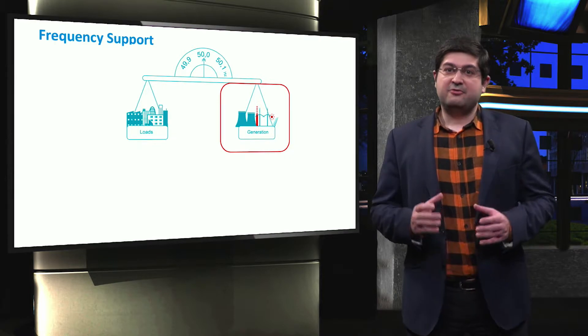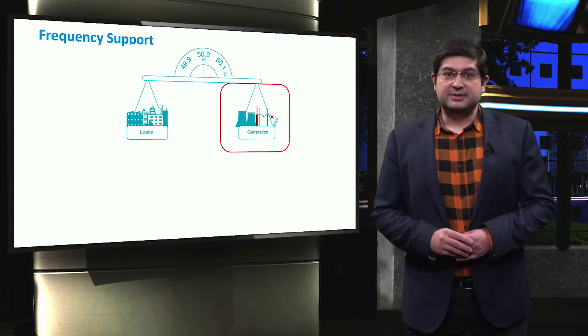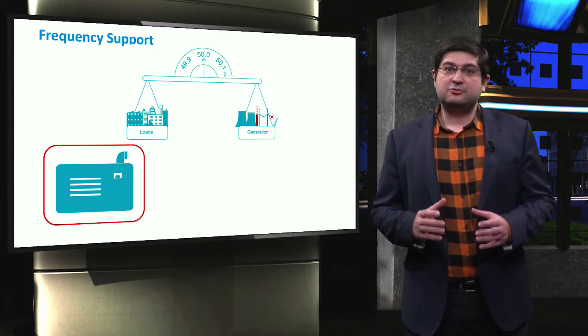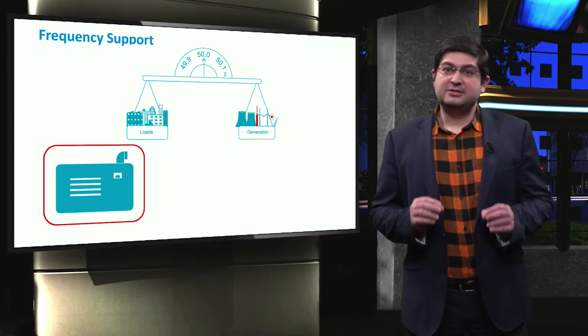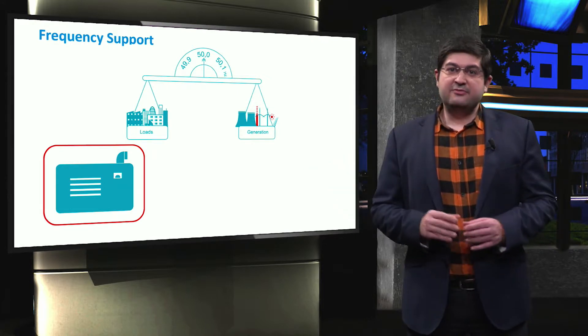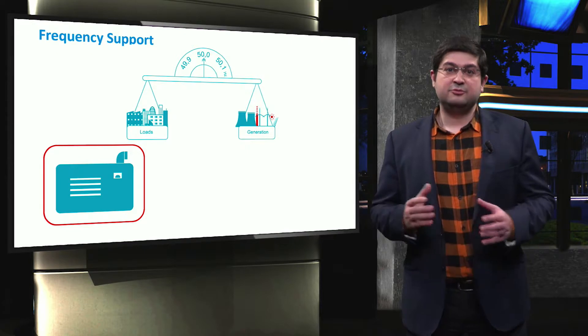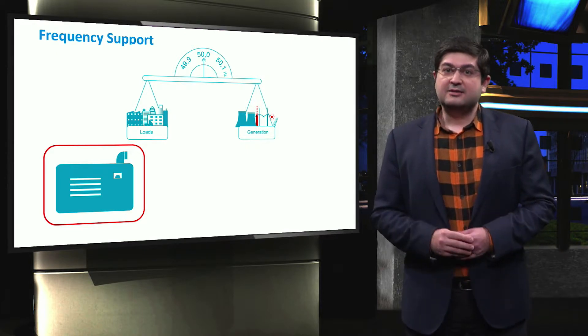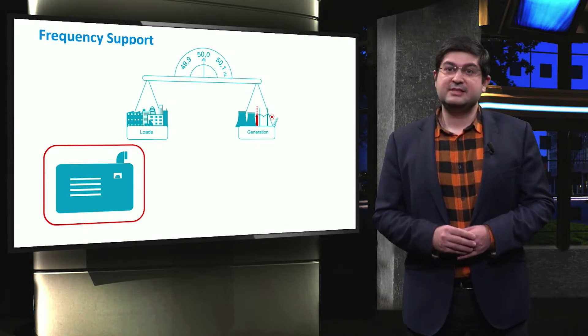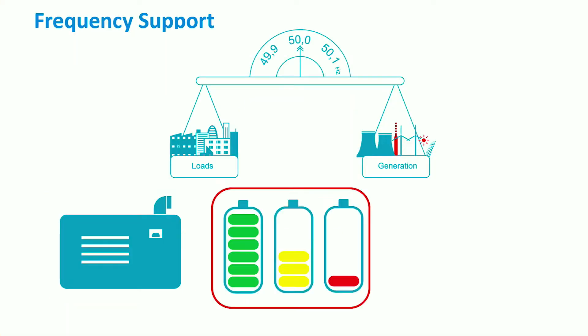The frequency can be controlled by various generating units or loads in microgrids. Diesel engines are able to control the frequency, particularly during emergency conditions, as a backup. If the amount of available fuel for a diesel engine is high, then they can continue with the islanded operation for a long period of time, for instance, for several days or weeks. Moreover, batteries are able to control the frequency mainly through their power electronic converters. The duration of the islanded operation by batteries will obviously depend on their size and the level of load consumption in the microgrid, as discussed in detail in the second week.